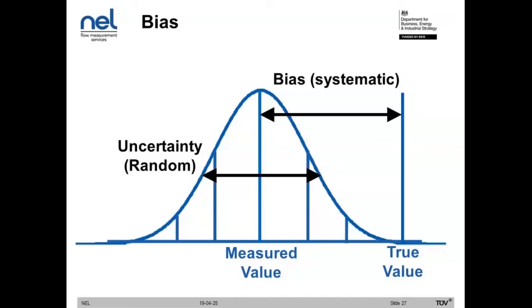So in this case, we have a systematic error that is introduced with every single measurement, in this case because of calibration of the device which is not performed correctly. So we still have a spread of results, it's just that they're nowhere near the true value of the measured parameter. And systematic bias occurs in many different cases, so it could be the calibration was carried out incorrectly, or it could be that the meter hasn't been zeroed correctly. That's a very common occurrence.